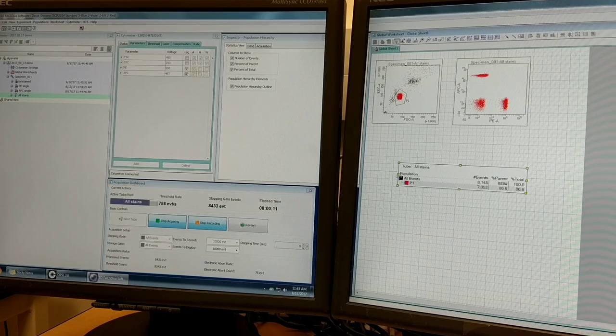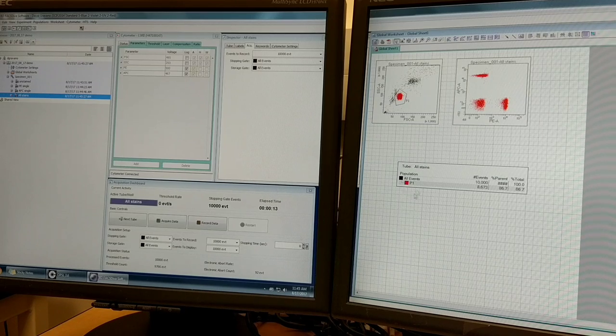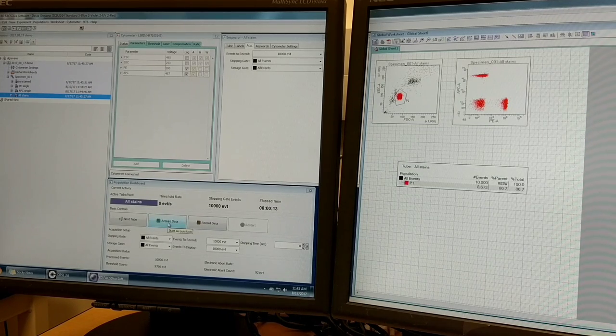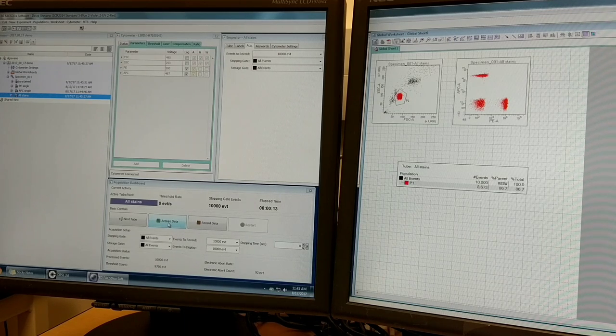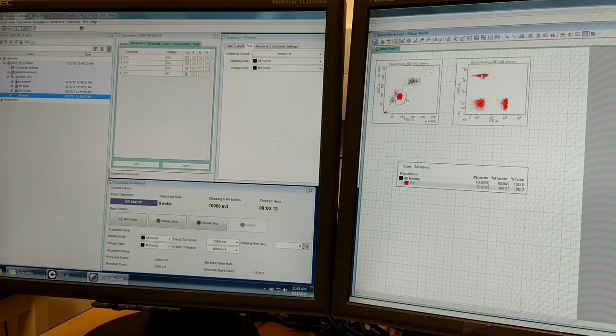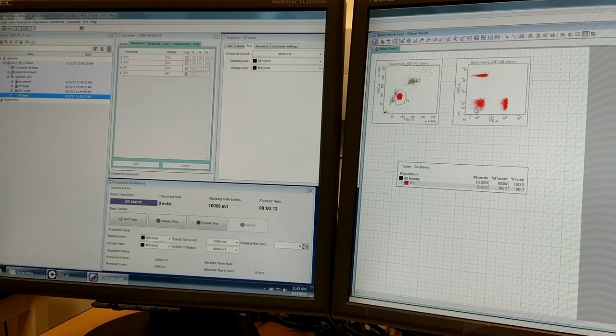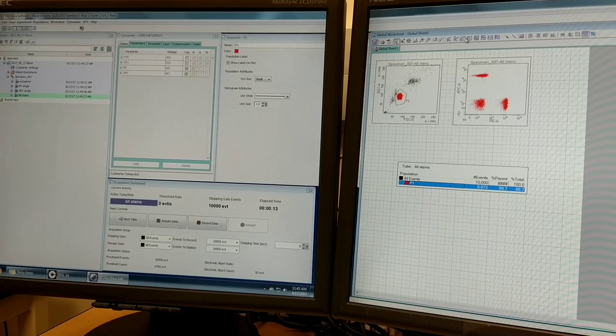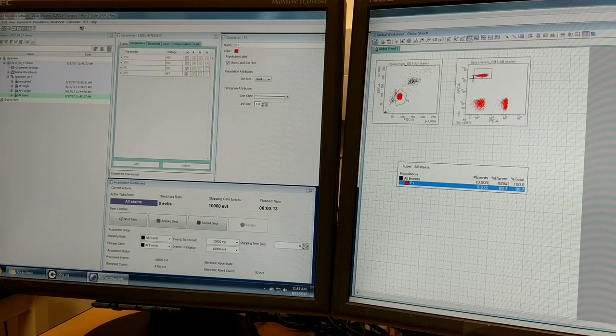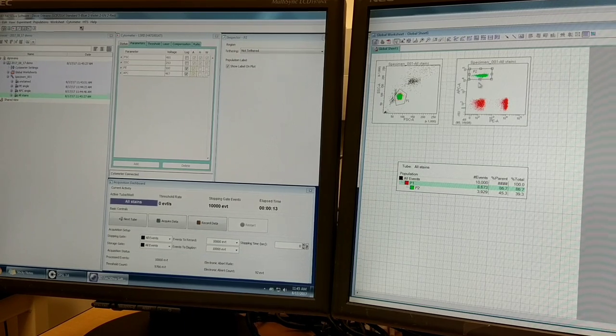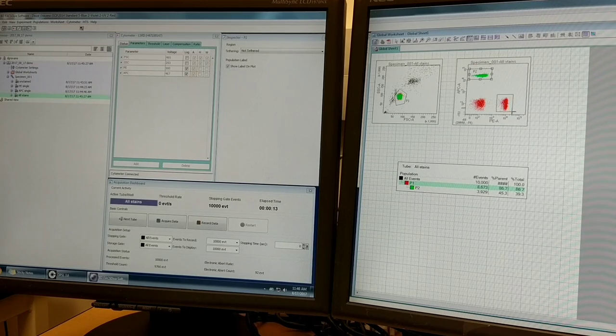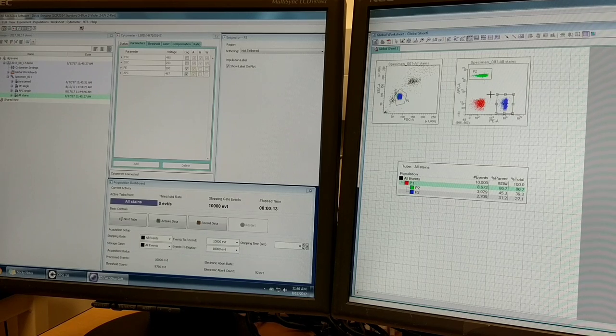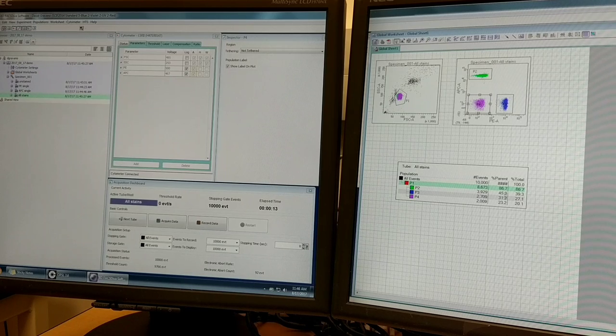What you can see in this plot here now is we can draw a gate. First, let's bring up our population hierarchy by going to population show population hierarchy. This will show you your gating hierarchy. We've got all events. Under that, we've got our P1 gate. Now, if under our P1 gate we want to gate these populations - the APC positive population, the PE positive population, or the unlabeled population - we can click on the P1 gate and then select your tool. I'll make a rectangle this time. That will be labeled P2. I can label just the APC positives, and I can keep repeating this process to select all the populations. I can easily see the percentages now of those populations within the sample.